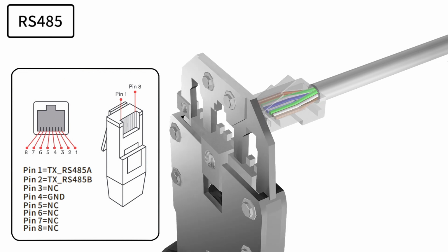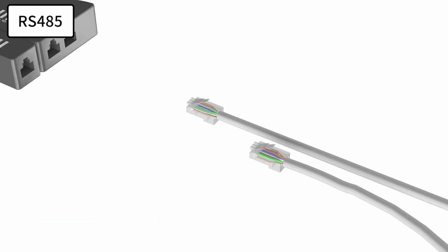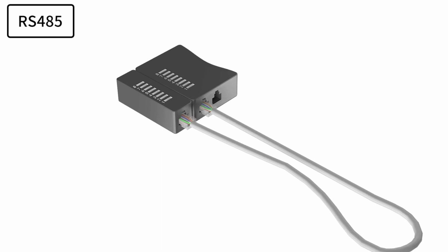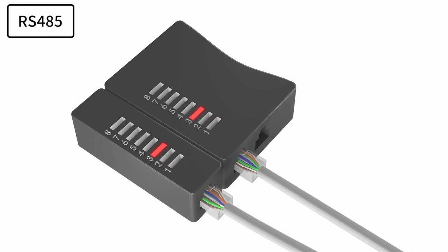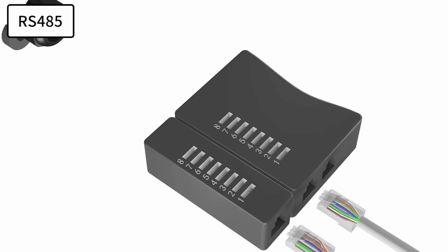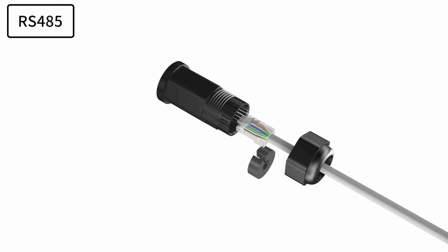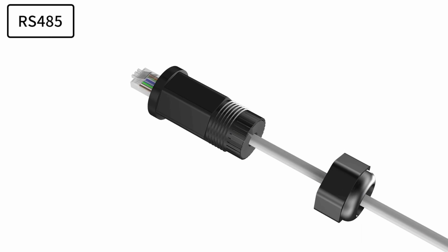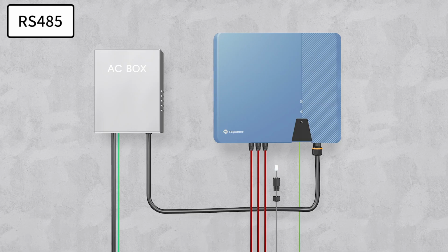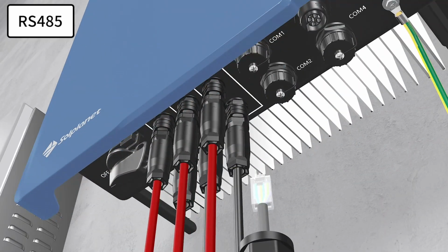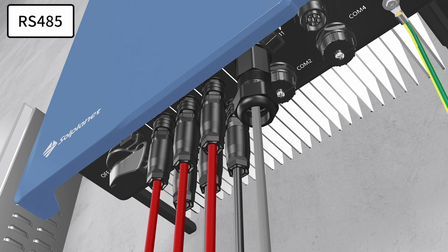RS485 cable pin assignment as below. Check the cable with the cable tester. Make sure the cable is connected. Lead the stripped cable through the cable gland and communication plate. Press the latch of the smart meter terminal and insert the stripped cable accordingly. Make sure the cable is connected firmly. Insert the cable into the socket.